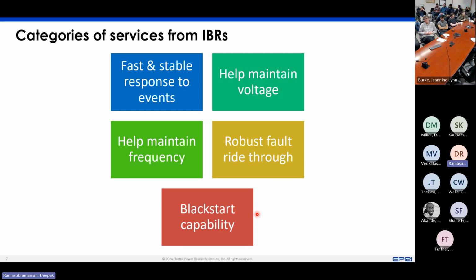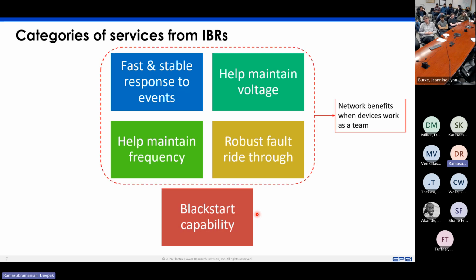Out of these five categories, four actually require the resources to work together as a team. Take frequency as an example—you can't expect one resource, one source, to be the frequency control for the entire grid. If we did that, we'd be using something like an isochronous governor control for all our synchronous machines, and they would fight with each other. Or we'd use isochronous governor control on just one synchronous machine and let it take care of everything.